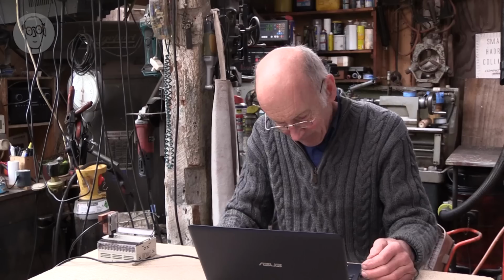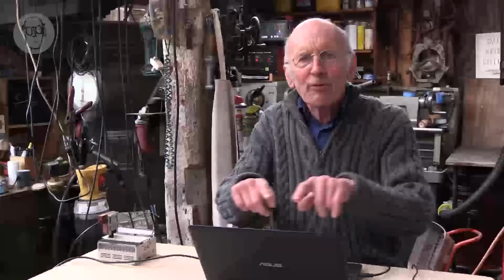It's called Stepladder Programming because it's almost graphical the way it's programmed, like a ladder with different rungs. On each rung, there's an input on the left side and an output on the right side. But these inputs and outputs aren't just the physical inputs and outputs on the surface of the PLC. They're more often internal relays, counters, timers and all sorts of other functions. And then you can have extra logic gates in the middle of each rung. The program runs through these rungs to the bottom of the ladder and then starts all over again, hundreds of times a second.